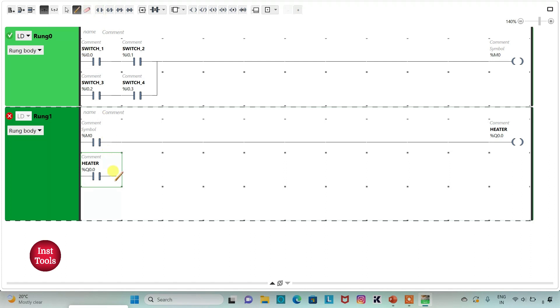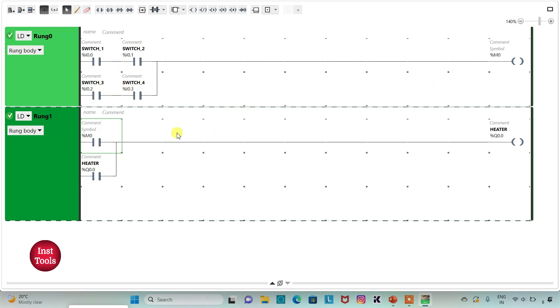I will draw a line to complete the latch. When switch 1 and switch 2, or switch 3 and switch 4 are turned on, M0 will be on. When M0 is true, the heater will be on. When those switches are turned off, M0 will go off, but because we have done latching here, the heater will still remain on. To turn off the heater, we will use switch 5, switch 6, switch 7, and switch 8.